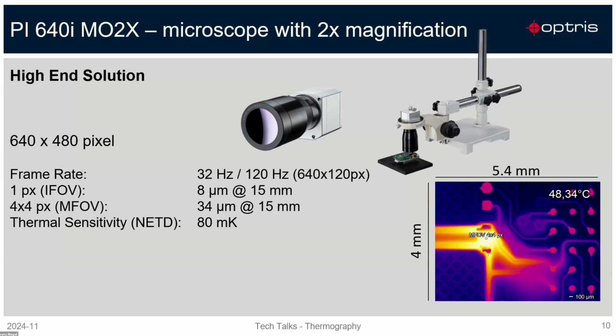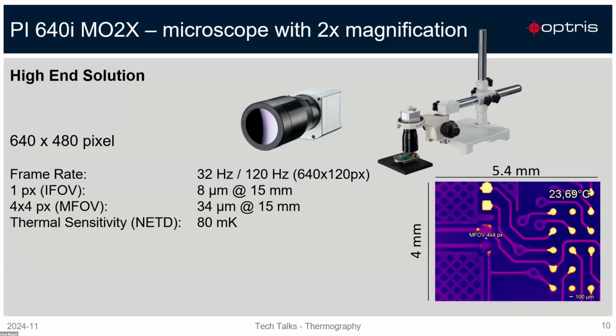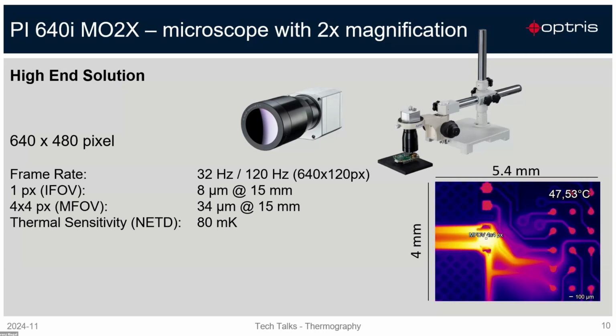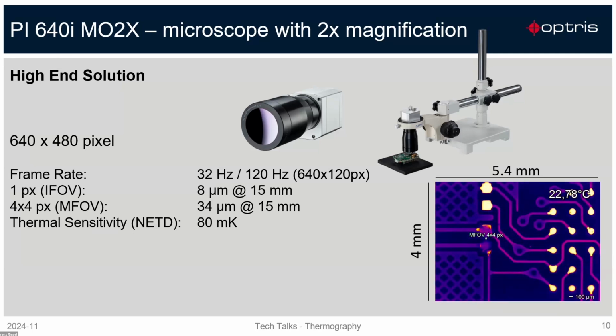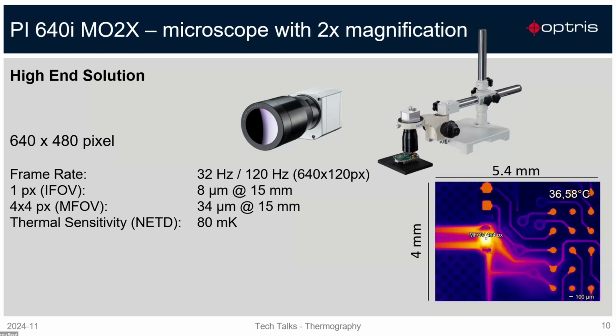And here you can also exchange the optic. So you can choose the standard optic, the MO44 optic, and for the high-end solution, you can also screw the microscope optic, the MO2x optic, in front of the camera. And here you can go down now to 8 micron. So this is for very, very small detailed components. And this is at a distance of 15 millimeter, where you have a horizontal field of view of 5 millimeter and a vertical field of view of 4 millimeter. And you have here also the thermal sensitivity of 80 millikelvins.